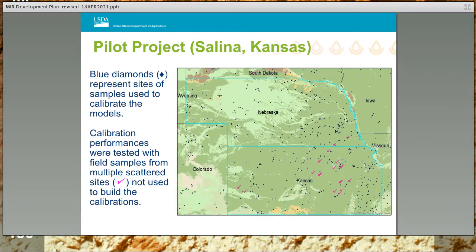NRCS first piloted this technology in Salina, Kansas. The blue diamonds represent archived samples that were used to build calibrations for various soil properties. The pink check marks represent true test samples collected after calibrations were made. The true test samples were not used for calibration and were brought back to the Salina field office, then dried, sieved, ground, and MIR scanned on the Alpha spectrometer. The MIR spectra collected on the Alpha were then processed through the calibrations to estimate soil properties. To assess calibration performance, the true test samples were then sent to the Kellogg Soil Survey Laboratory for conventional measurement of soil properties being estimated from MIR.